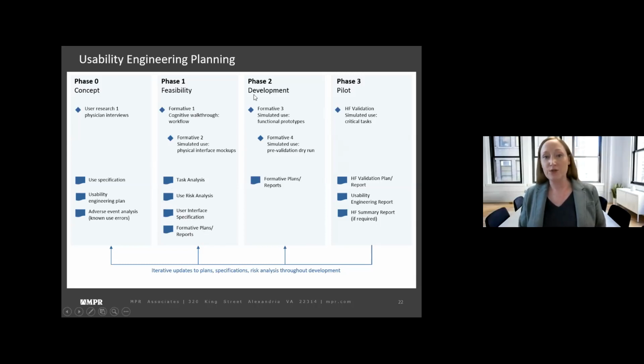As we transition into phase 2 development, it's typical to have formative studies on the more integrated functional prototypes that are starting to come together. And then finally, in phase 3, the pilot phase, that's when your human factors validation study would be performed and the associated report. There will also typically be a usability engineering report that's analogous to the risk management summary report, that documents that we did everything we said we'd do in the usability engineering plan and summarizes the outputs of our usability engineering file. It might also be necessary to put together a more detailed human factors summary report if that is necessary to include as part of your FDA submission.